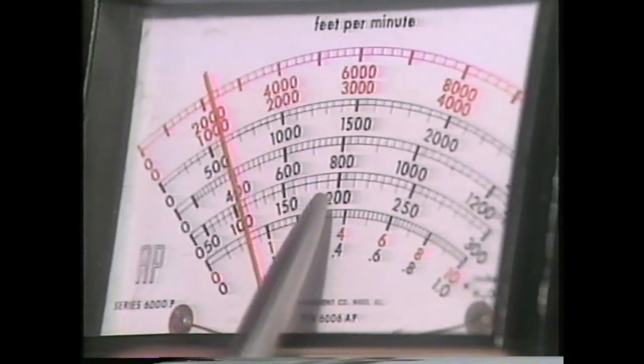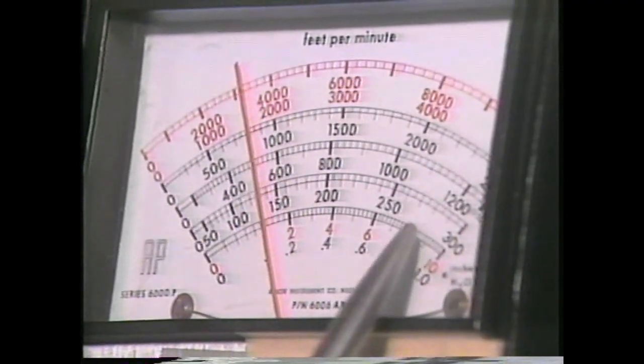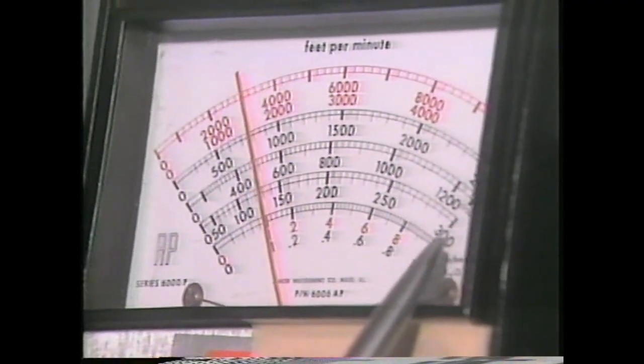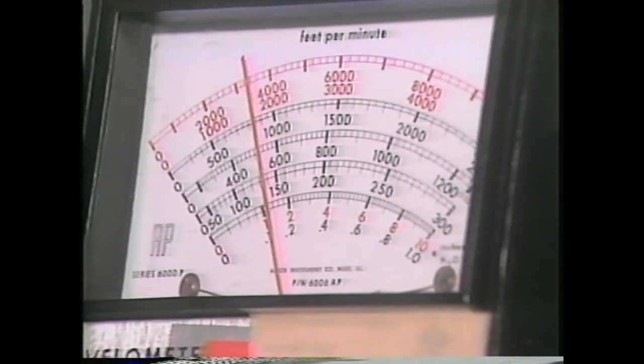Both of these velometers are designed to take measurements of the air velocity by pointing either probe arrow in the direction of air flow. The opening of either probe should be parallel with the air flow. If the direction of the airflow is uncertain, either probe should be rotated to obtain the highest reading. The highest reading would indicate proper positioning of the probe in the airflow stream. While measurements are taken, the needle on either device will fluctuate. After observing the fluctuation, a range of movement should be noted. An average of the range of the movement should be recorded for the reading.